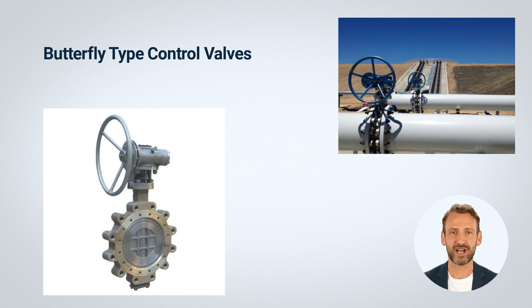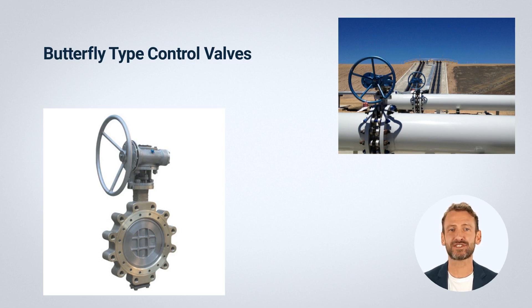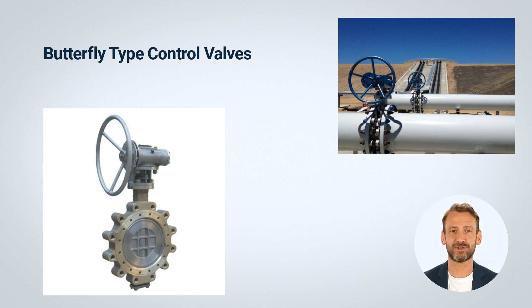Pros and cons: advantages of butterfly valves include ease of operation, low cost, and suitability for large-diameter piping systems. They require less space and weigh less than other valve types, making them easier to install and maintain. However, butterfly valves can suffer from poor throttling characteristics and have a limited temperature and pressure range. They may not be suitable for certain fluids or high-pressure applications. Overall, butterfly valves offer a cost-effective and efficient solution for many flow control applications, particularly in large-diameter piping systems.